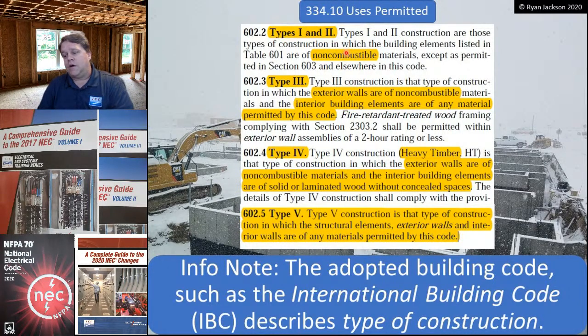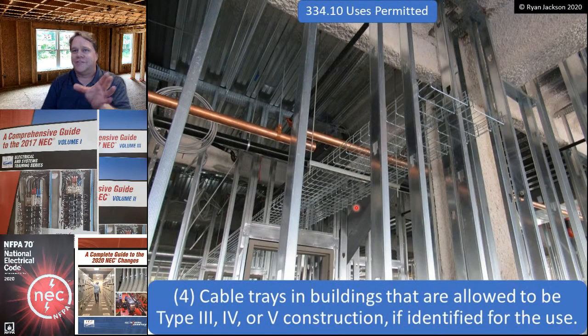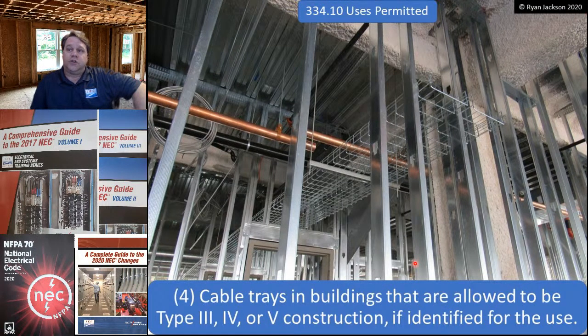Types 3, 4, and 5 allow wood to some extent, to varying extents. Type 3 allows some wood. Type 5 allows complete and total wood. So how much wood doesn't matter for us electricians. If there's any wood in the building, you can use NM cable. That's the rule of thumb. I know that's overstating it slightly. There are some exceptions. You can put it in cable trays. Kind of strange, but you could. Cable trays in buildings that are allowed to be type 3, 4, or 5 construction, if identified for the use. So the cable actually has to be identified for cable tray use.